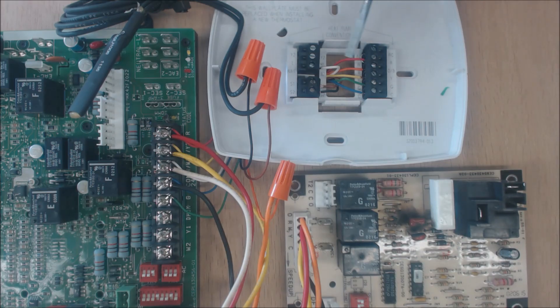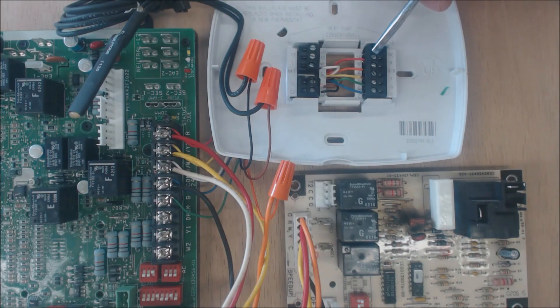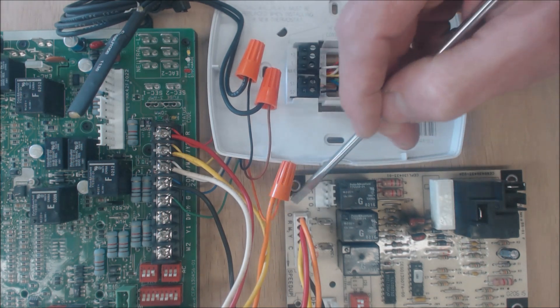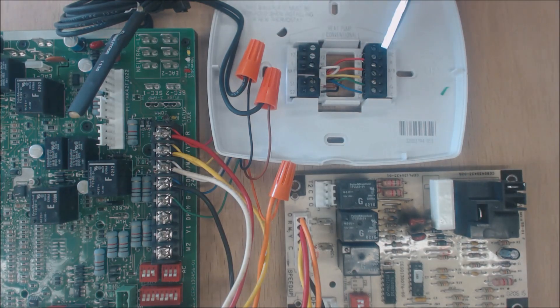For heating, 24 volts comes from red to R and then touches W, which turns the blower motor on at its higher fan speed, and 24 volts goes from R to G. In heat mode, O is now non-powered, which means you are in heating mode for most general manufacturers. You would set it in the program if you wanted to run it as B, which would power the orange wire in heat mode, but most of the time you're only powering O in cooling mode.